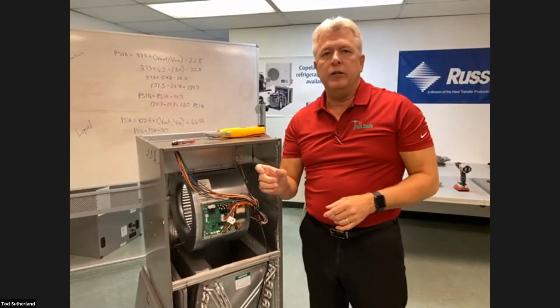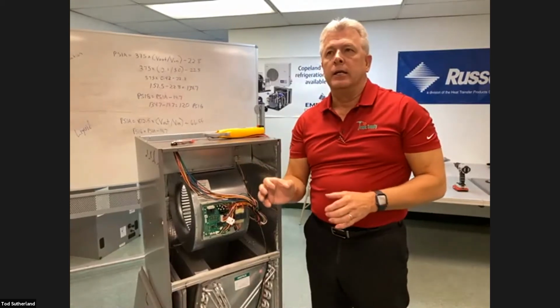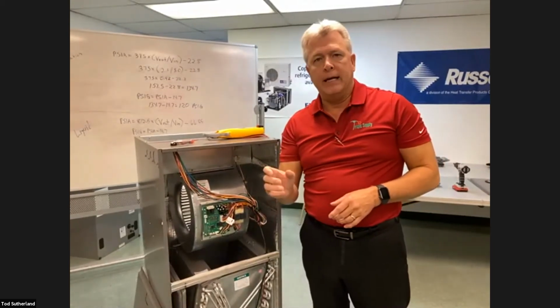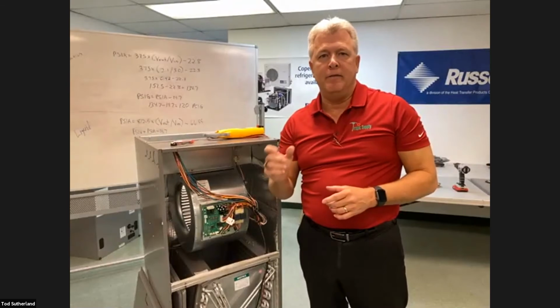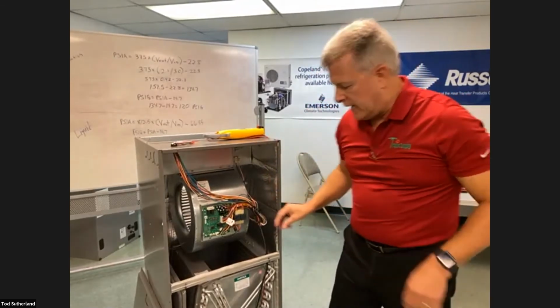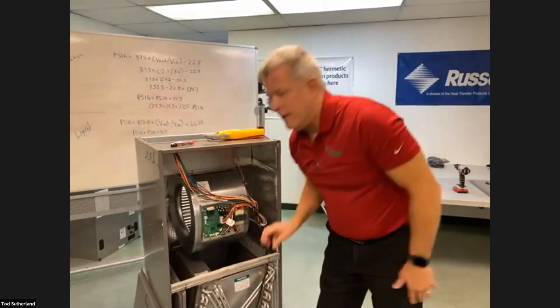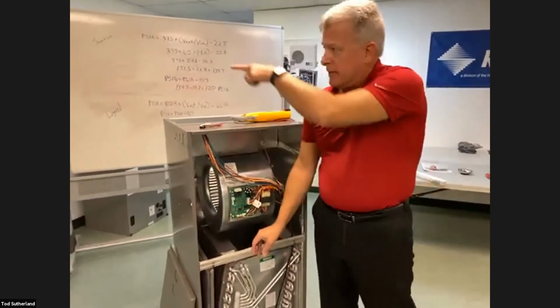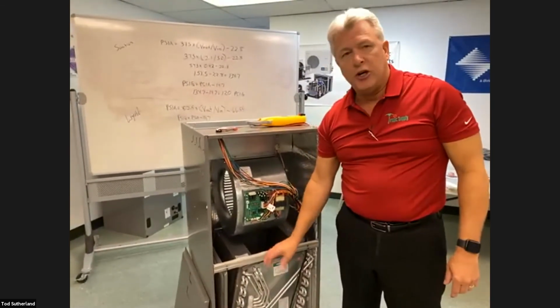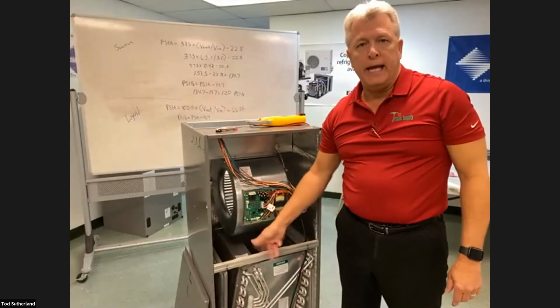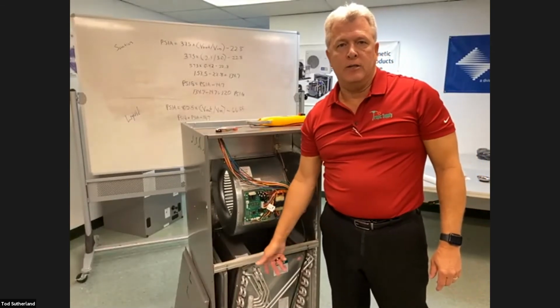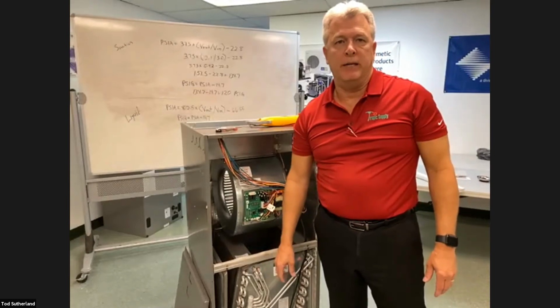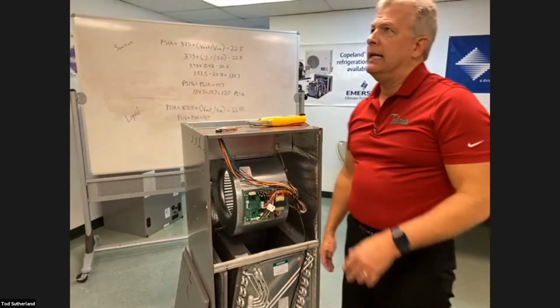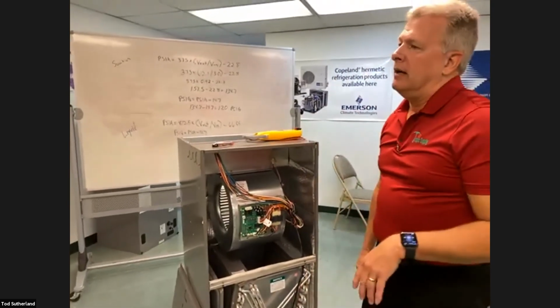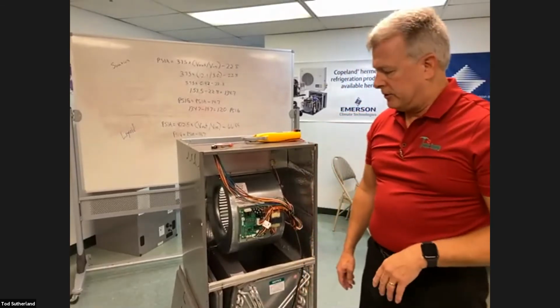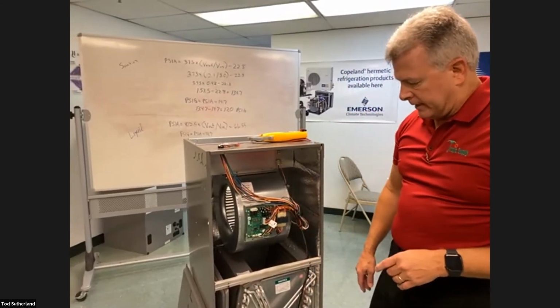Now you've got to be careful that you get the EEV magnets, because there's also a solenoid magnet that functions differently than an EEV magnet. But the EEV magnet, you can pull that stepper motor off, slide the EEV magnet over that expansion valve stem where the motor is, and then you can turn that magnet and it will open or close that valve. So you can't really adjust it, but you can open or close that valve in a pinch. Can't tell you off the top of my head who sells those, but we can get that information to you. They're a great tool to have.